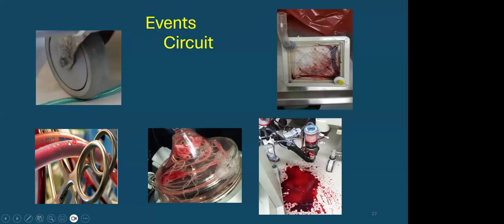Cavitation. So with excessive negative pressure, air can actually almost be formed, if you like, in the venous limb. This has to be prevented at all costs because this air will go towards the pump, and if it gets in between the magnet and the head, that pump will essentially not spin, and the flows will drop, and that has to be evacuated as an emergency. Accidental disconnections are obvious. This literally was disconnected for a second, and that's how much blood fell onto the floor. We very seldom do this now, this was at a stage when we were moving patients to the operating room for decannulation. We don't do that at all now. We do decannulation at the bedside, just to minimize adjustments, not just in patient position, but also ventilation, etc.